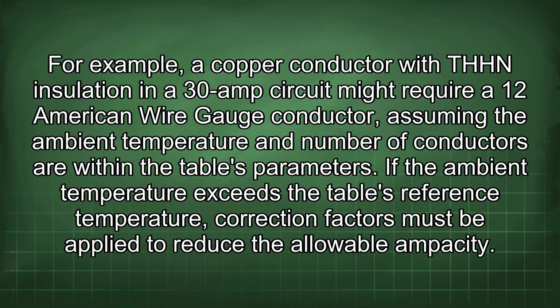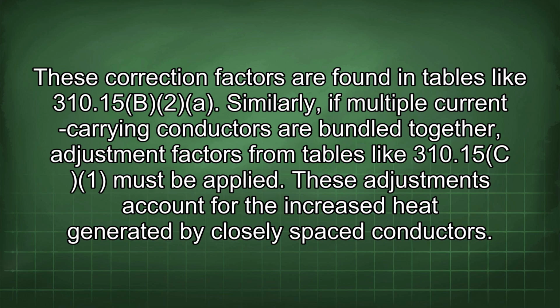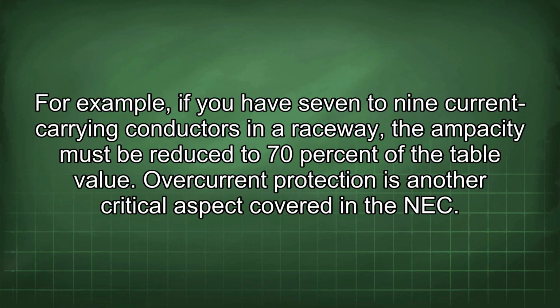If the ambient temperature exceeds the table's reference temperature, correction factors must be applied to reduce the allowable ampacity. These correction factors are found in tables like 310.15(B)(2). Similarly, if multiple current-carrying conductors are bundled together, adjustment factors from tables like 310.15(C)(1) must be applied. These adjustments account for the increased heat generated by closely spaced conductors.